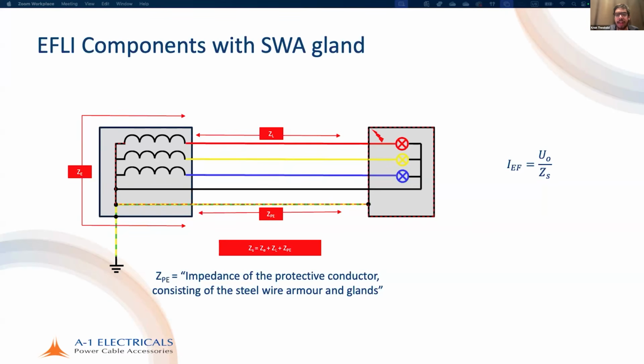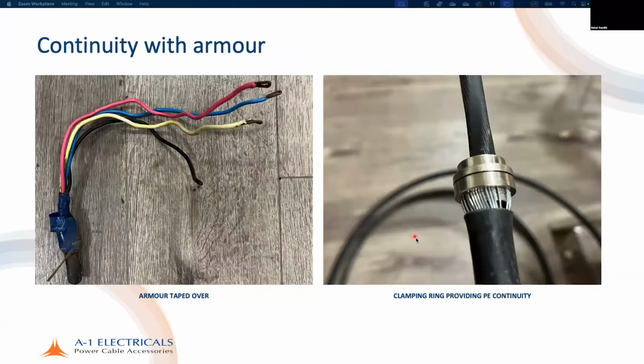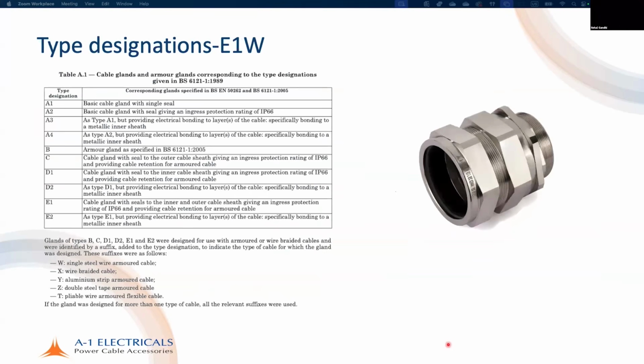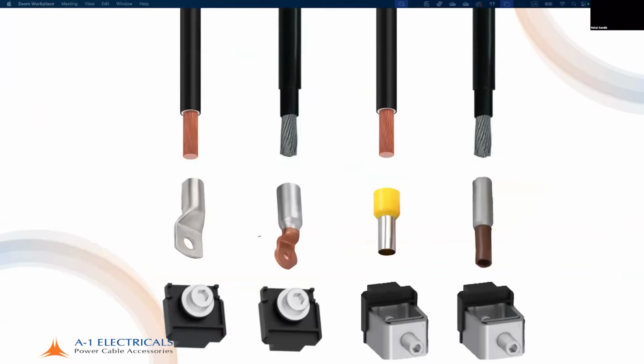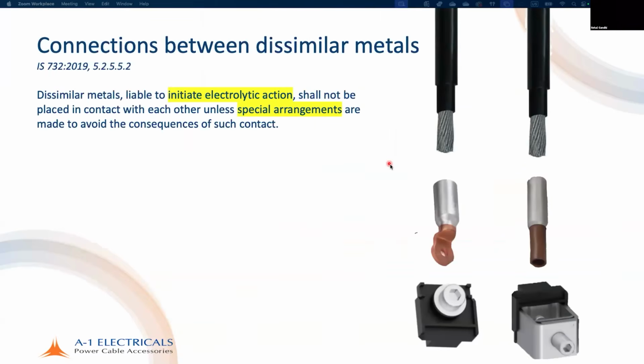Mr. Sunil Kumar VK is saying, instead of bimetallic sockets, I think he means lugs, there is a practice of using a bimetallic strip between the socket and the conductor when dissimilar metals are used, for avoiding galvanic corrosion. I don't believe this is adequate, Mr. Gandhi. It can be adequate, subject to it having proper thickness and everything, proper sizing, proper selection. Because it's not general. What people normally do is put a small copper strip and aluminum strip and use it, which is not correct.